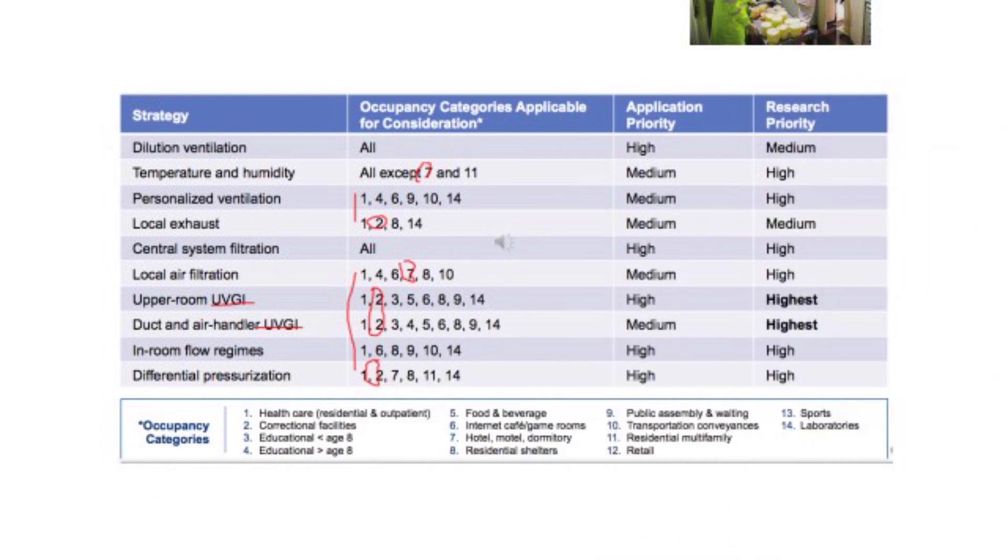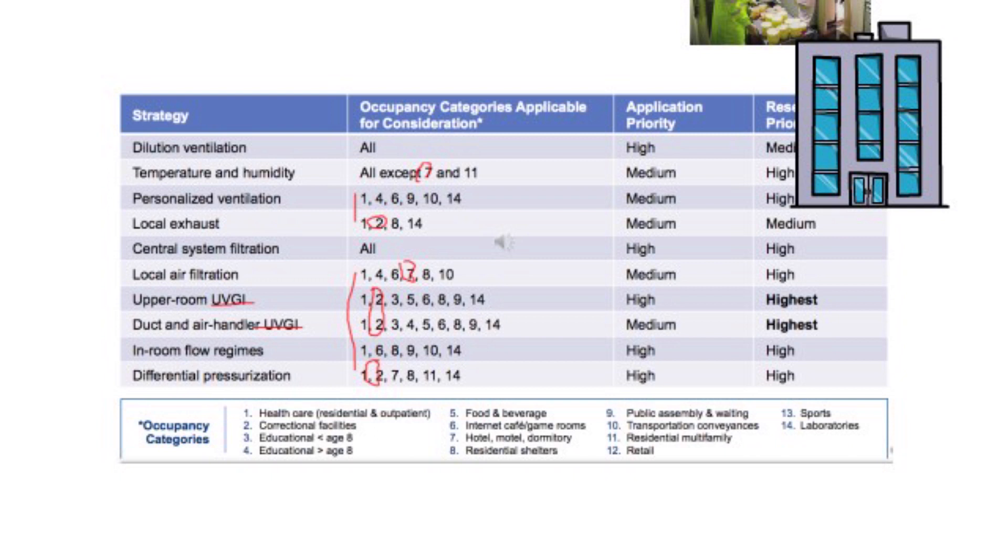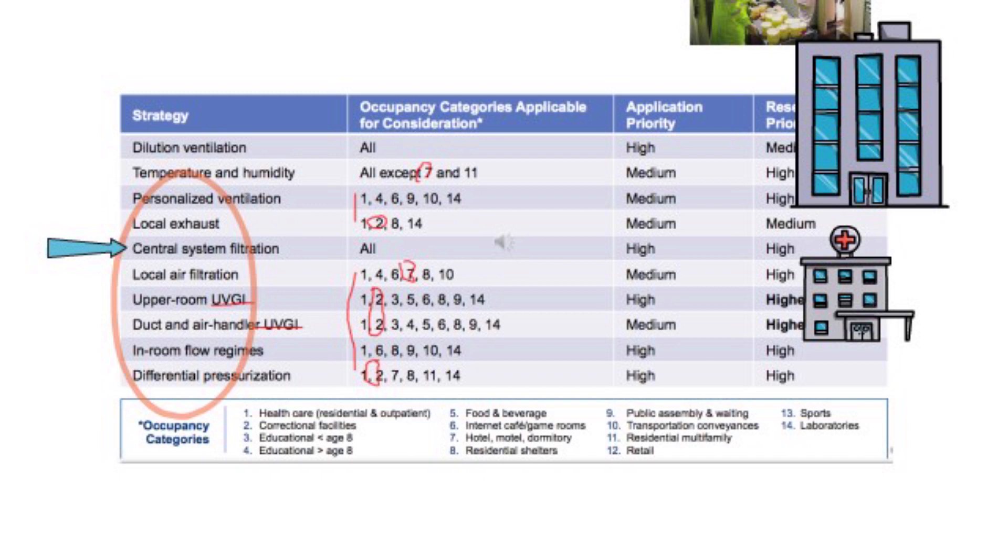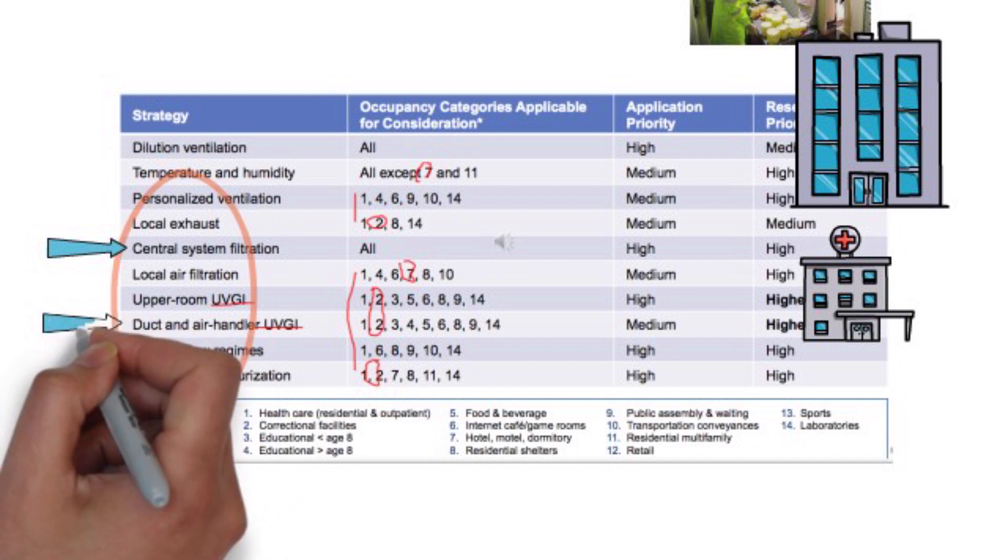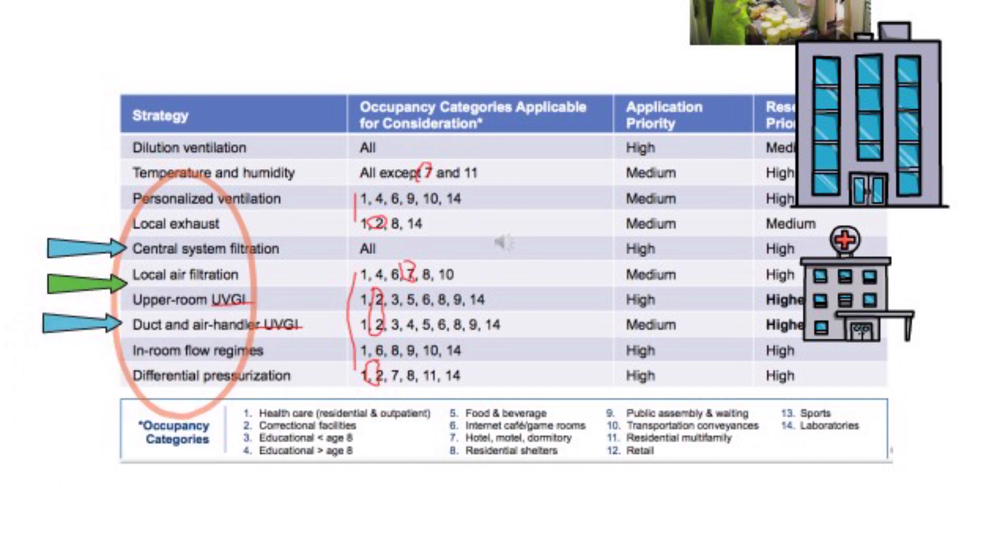This table from the ASHRAE document is very useful. For each of the 14 building types, number one is health care facilities, number two is correction facilities, etc. What control strategies apply, and what are the application and research priorities? We can see that for health care facilities, all strategies apply. Dilution ventilation, temperature and humidity control, local exhaust. If possible, you can also use upper room UVGI and local air filtration to kill or filter viruses.